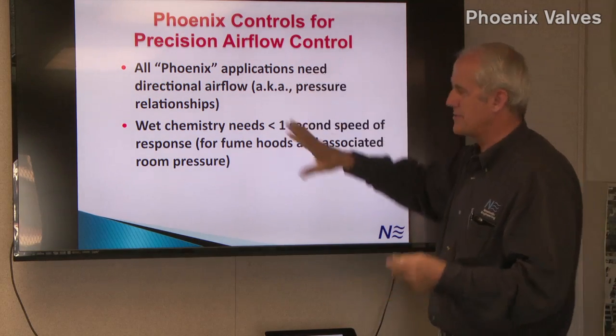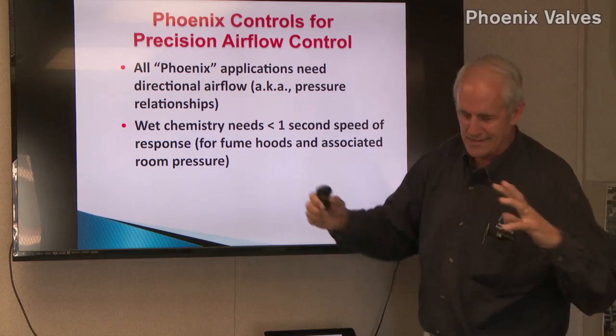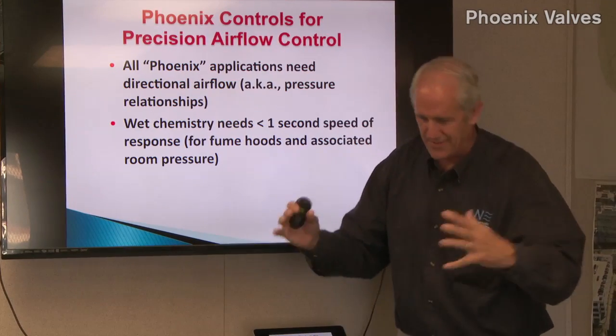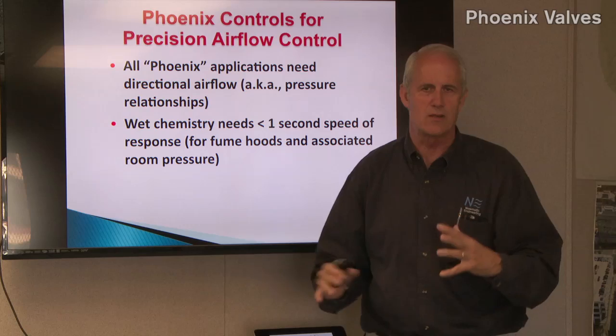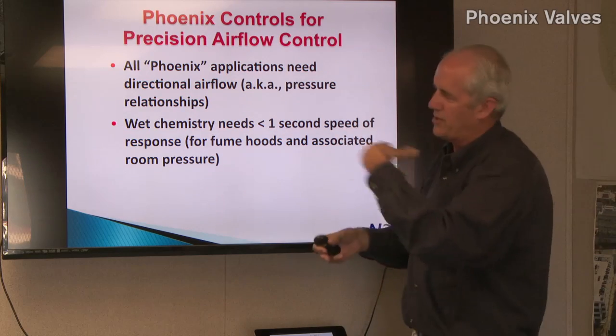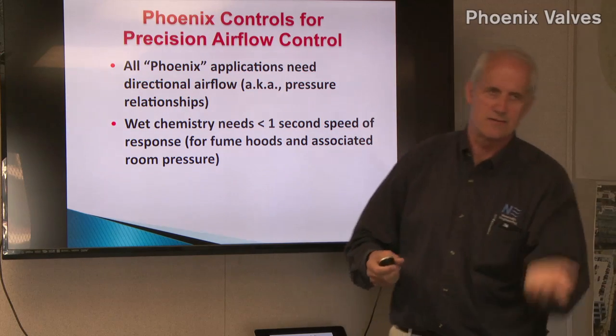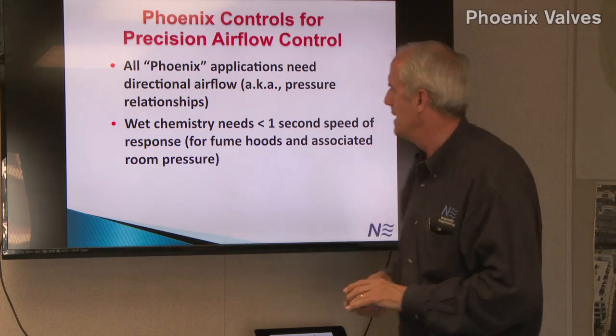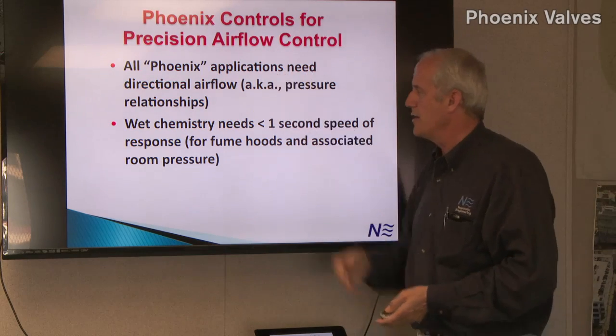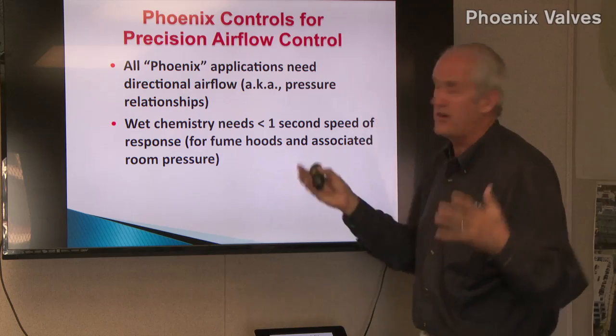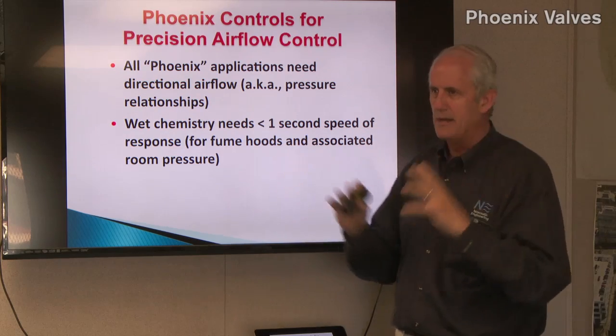Anywhere where you use Phoenix, directional airflow matters. That means the positive room should stay positive, the negative room should stay negative, something like that's going on. If you don't care whether the door is blowing or sucking, you don't need Phoenix, just go with a VAV box. But the fact that you're using it here means the directional airflow does matter. And in a vivarium, it's really important that you maintain proper pressurization.